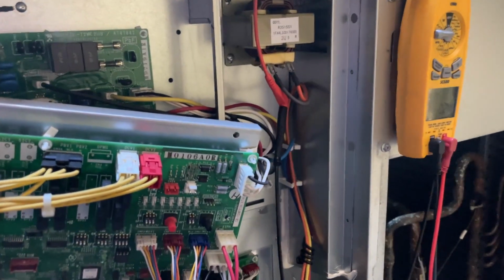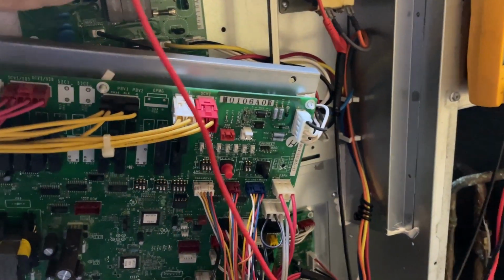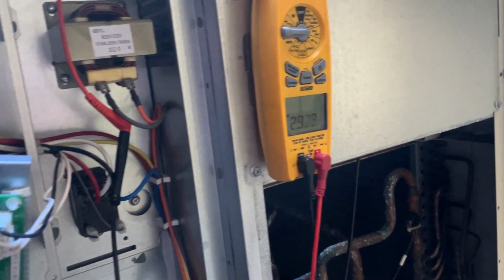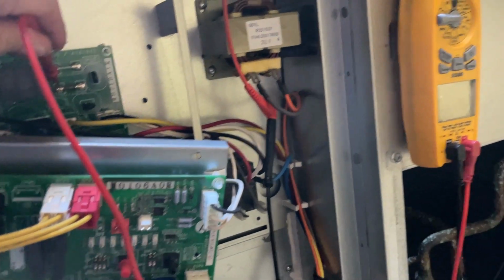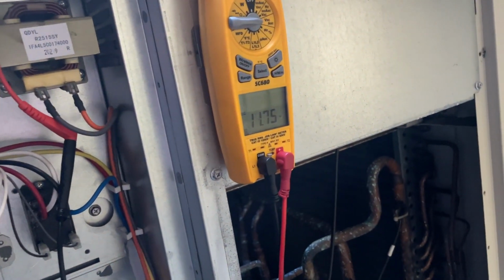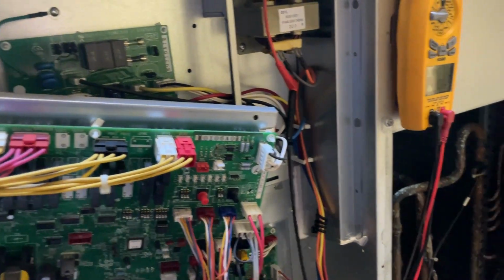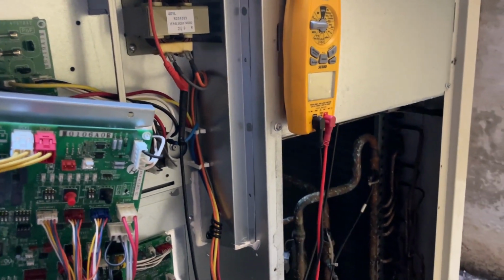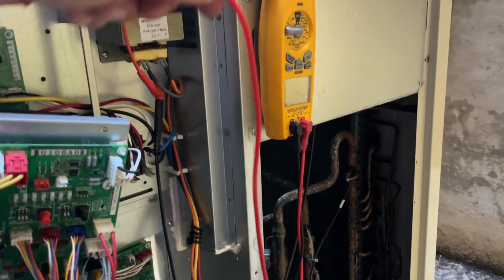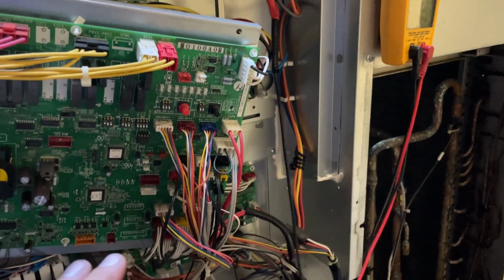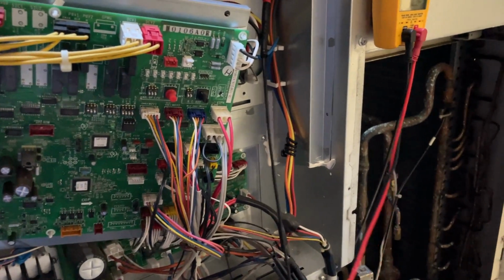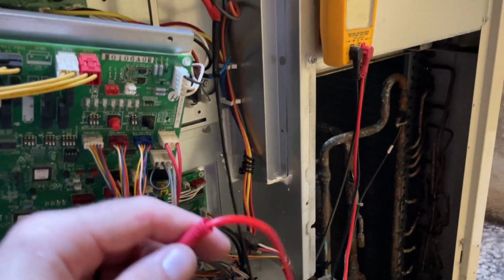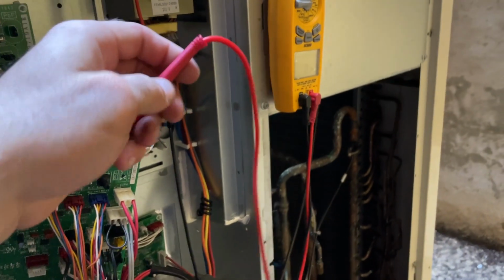Quite a bit of time has passed and I'm still reading voltage on that side and that side, probably just due to back feeding. But that goes to show how long these units take to fully discharge, and that's why when you do power cycles, you want to leave them off for about half an hour before flipping it back on.